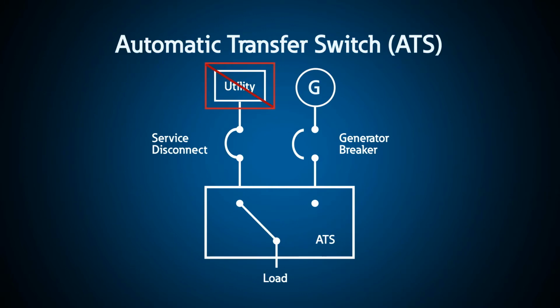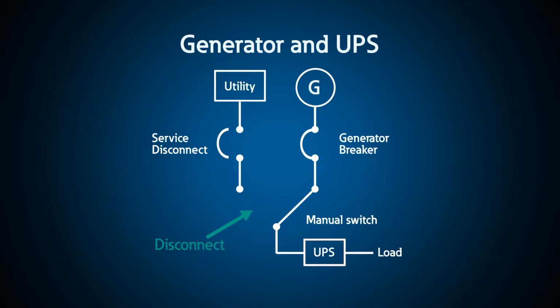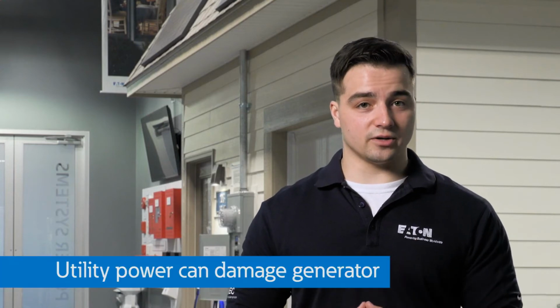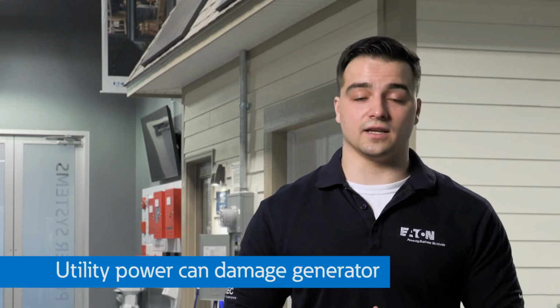A more advanced generator setup would start automatically and have an automatic transfer switch to open the connection to the utility. Make sure that you have a circuit setup that ensures you are disconnected from the utility when the generator is running so you don't backfeed power and put utility workers at risk. Also, when utility power comes back, it would destroy your generator and could cause a fire if not disconnected.